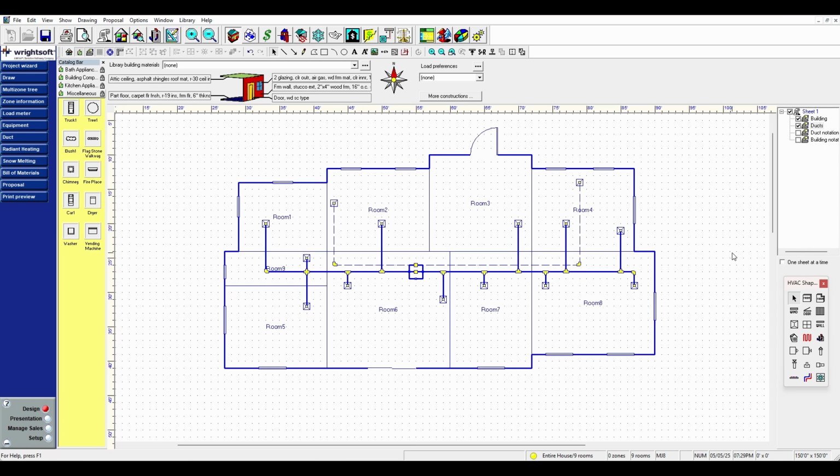So for these ducts here, for the supply line, the limit is 900 feet per minute. That's the speed of the air moving inside these ducts. For return air, that's the air inside of these dashed lines, the limit is 700 feet per minute, which means that we will require larger ducts to slow down the air.